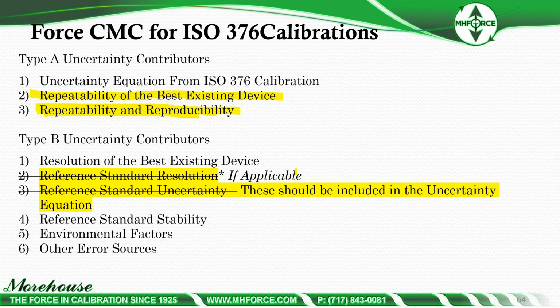that's an if applicable, but reference standard uncertainty, this is usually included, but ISO 376 already includes it, so it's included in the uncertainty equation, so you don't have to deal with it. Same with reference standard resolution, that's already included in the ISO 376 stuff. Reference standard stability, often missed. Not many documents talk about stability the way they should and the way it contributes. It is usually very dominant when you do an uncertainty analysis and you look at drift from one calibration to the next. So that needs to be included.